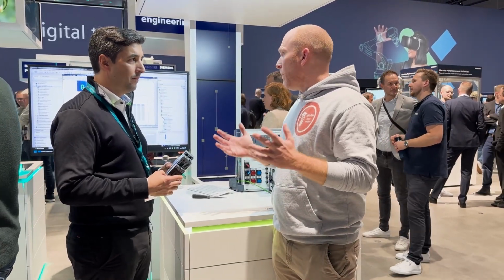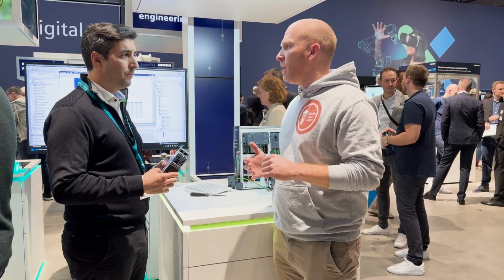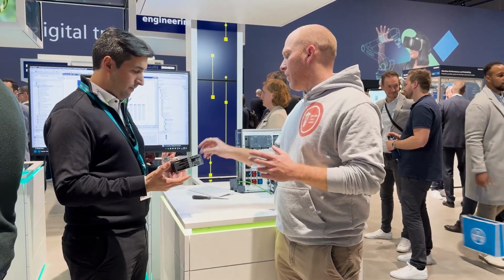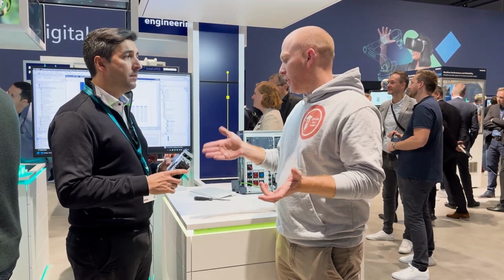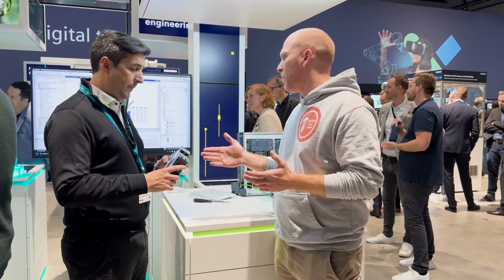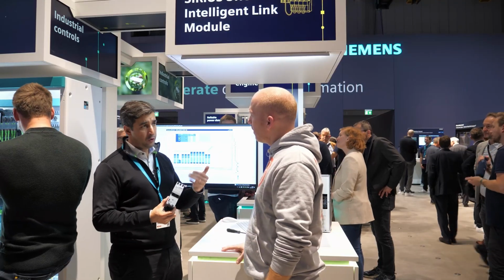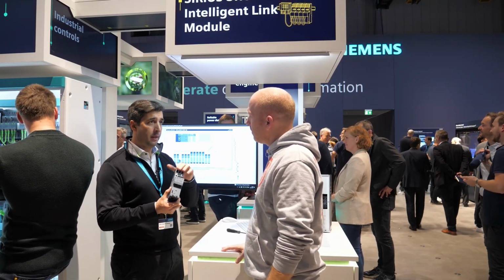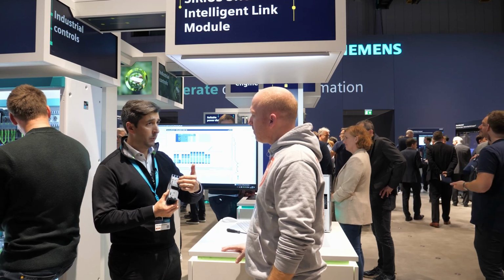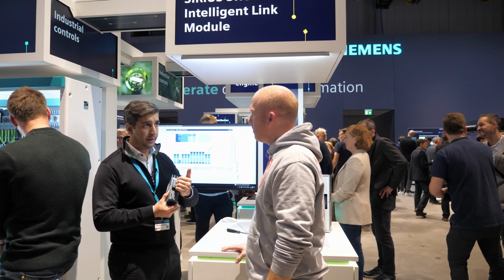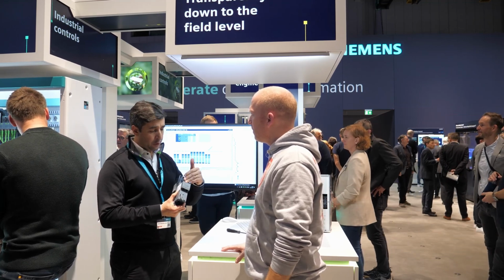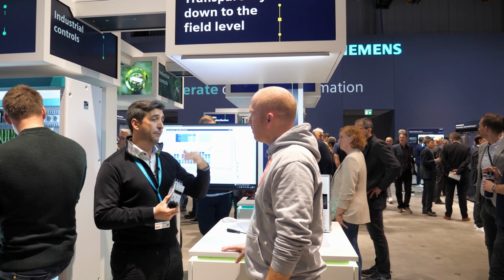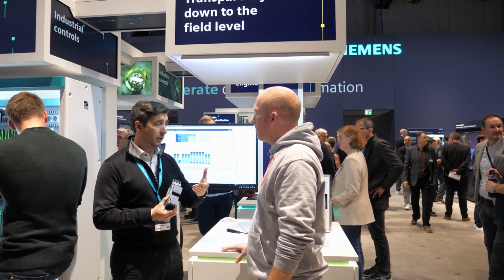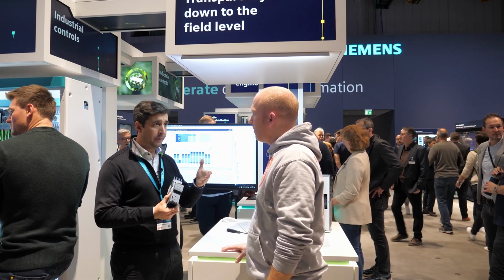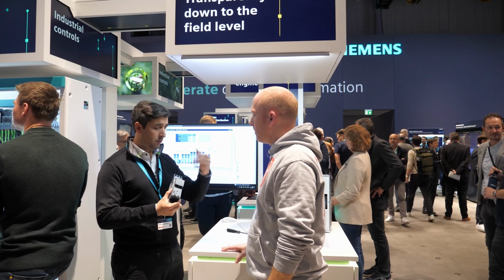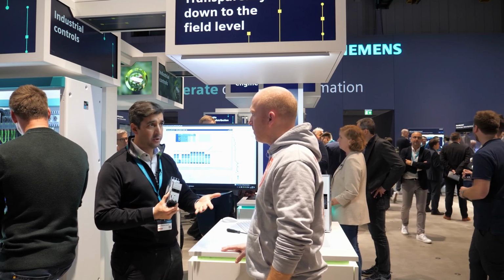Yeah. For revamping projects, when I already have a motor protection device and have done some settings, I have an additional setting in the intelligent link module, right? Well, you can do two things. If you already have an overload protection in the device, you can just deactivate the overload protection in the ILM. But for sure, you keep all the rest of the diagnostics, like phase imbalance and so on. You can also monitor the status of the contactor and check all the power consumption.